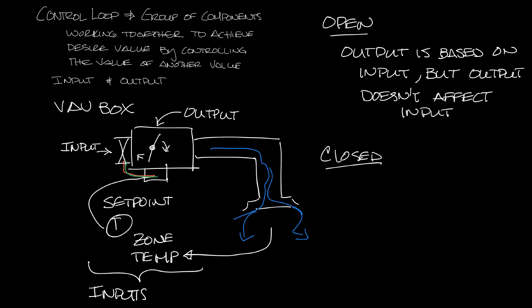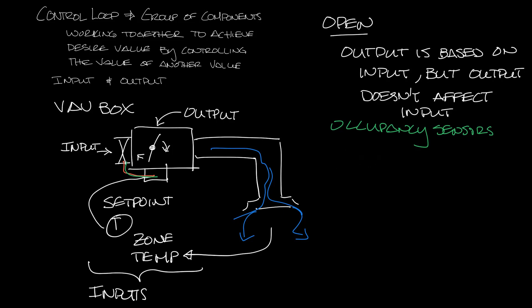An example of an open loop would be the use of occupancy sensors to control the schedule of a VAV box. Let me get rid of closed for now to make a little bit more room. Another example of an open loop would be using an outdoor air temperature sensor in your control loop.